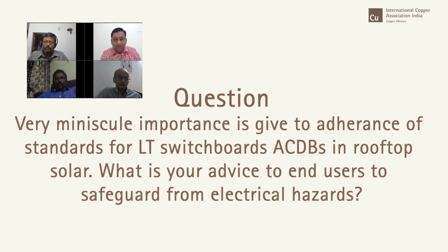Any switchboard manufacturer will comply with the standards for manufacturing of the switchboard. So there is actually no specific IS which applies to the manufacture of LT switchboards. But the only issue is, depending on the place of installation of that switchboard, the protective features come more into picture. One is you have to have those surge protection devices, considered in accordance with the type requirement of that surge protection device. So that alone is the additional feature, nothing beyond that. Okay, but from a safety perspective, what would be your message for the end users as well?